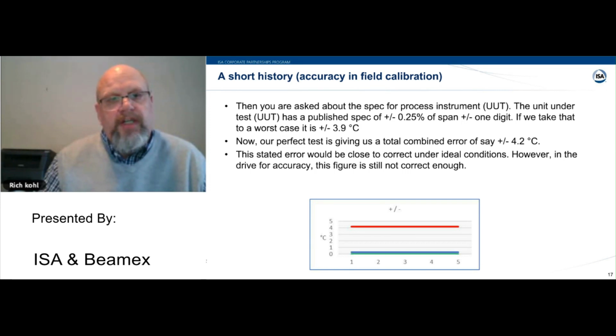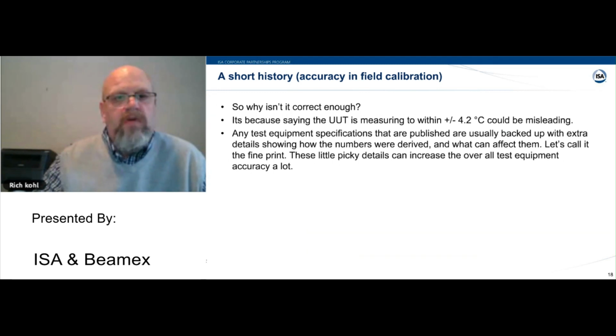What we're seeing here is from the point of view of the process measurement. That's the end result of your calibration in the process instrument going. And you see we have a big jump in accuracy represented by the red line. So why isn't that good enough?